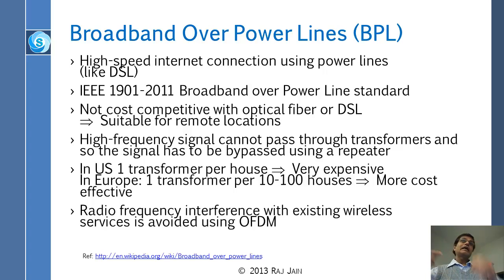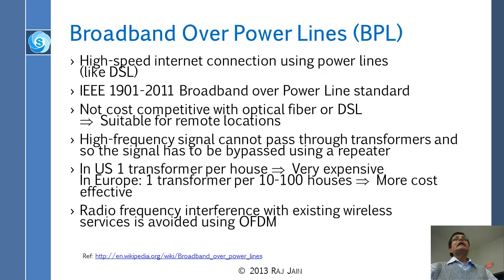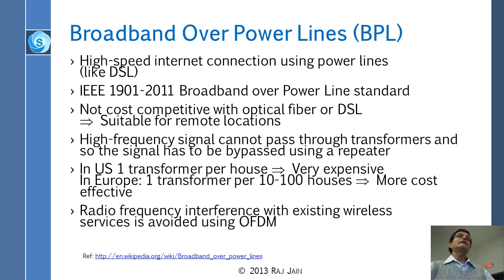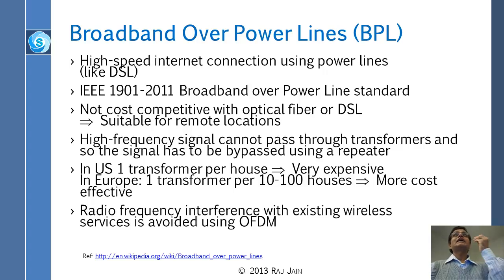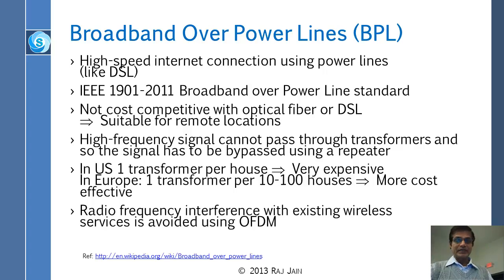The reason BPL failed in the US is that we have too many transformers, and radio frequency signals don't pass through transformers. We have roughly one transformer per house — there's a big pole next to my house with a transformer that brings electricity to me. In Europe, one transformer serves 10 to 100 houses. To deploy BPL in the US, you'd need a repeater around every transformer, which is very cost-ineffective — you'd need a truck roll for each connection. In other countries, especially where people live in high-rise apartments, one transformer can serve 100,000 apartments, making BPL very economical.